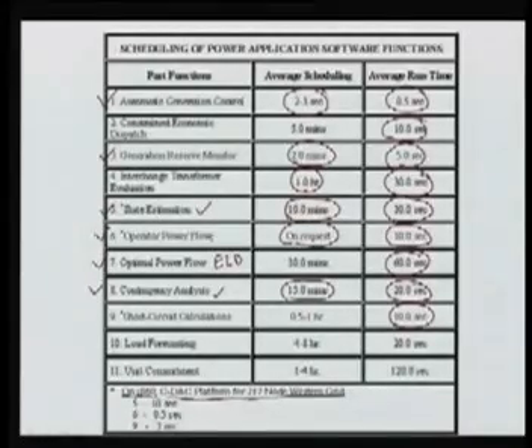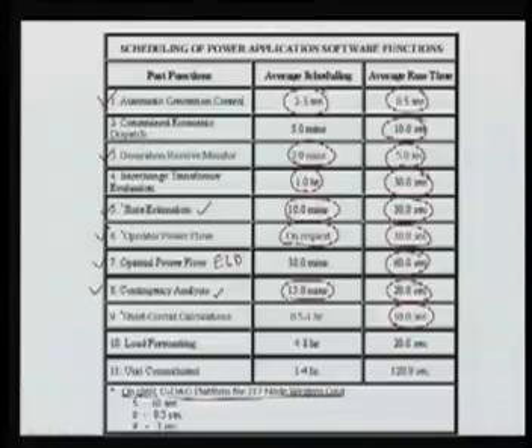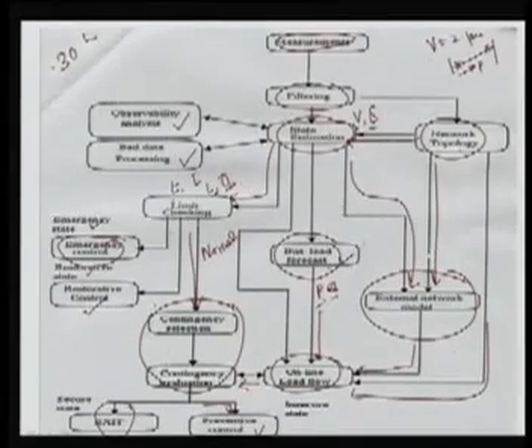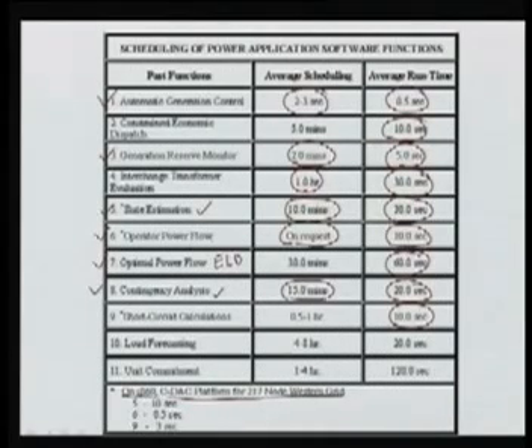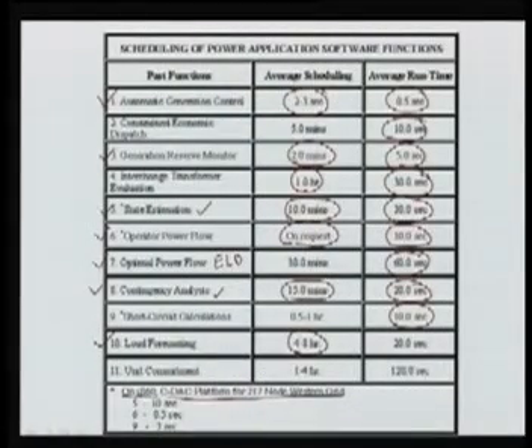Load forecasting. Again, load forecasting can be done in different fashions. It can be long term, medium term, or short term load forecasting. This short term load forecasting can be categorized at various intervals: it may be for 1 day, it may be hourly, it may even be half hourly, as we saw in the previous section. Other load forecasting functions may require half an hour so that the operator can schedule the generating stations accordingly. So it may require 4 to 8 hours for the average scheduling, but the computational time requirement is very fast, that is 20 seconds.